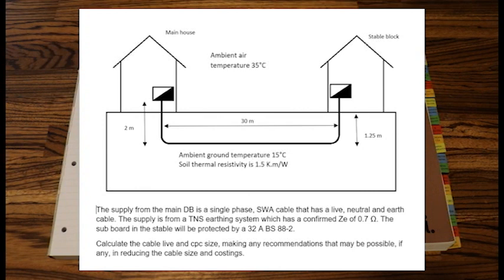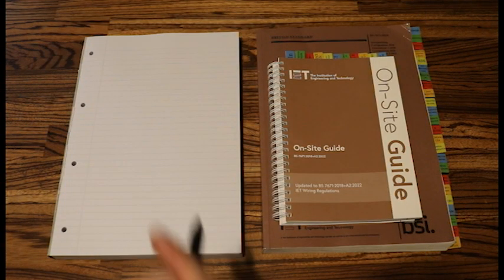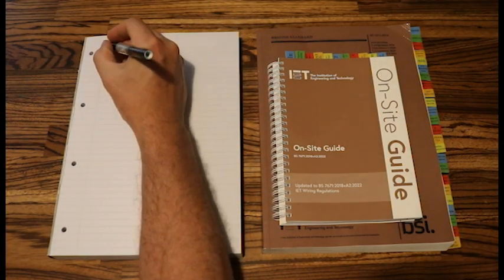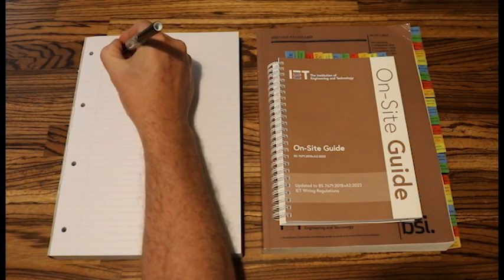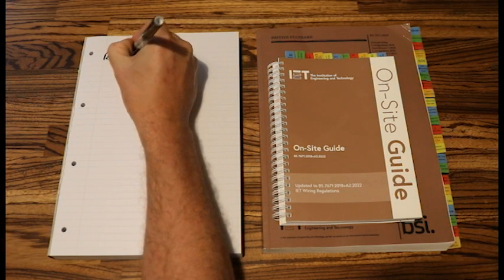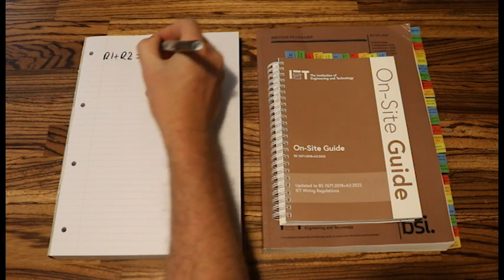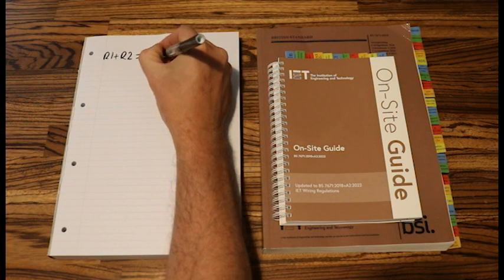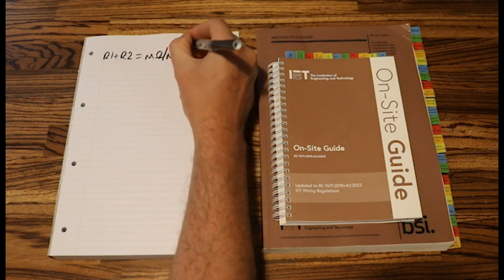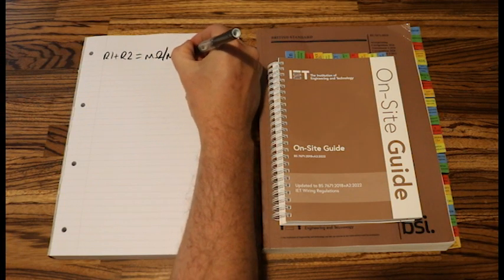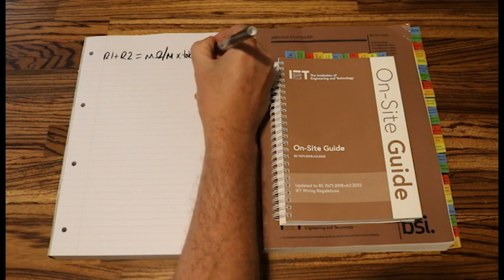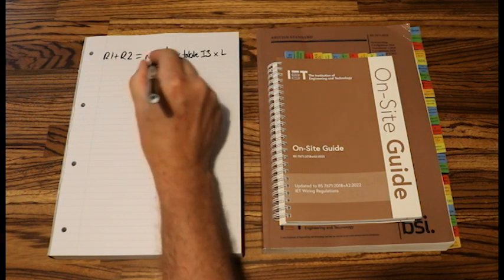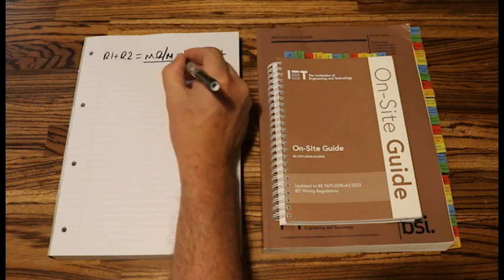So we need the formula for R1 plus R2. The formula is milliohms per metre times table I3 times length all over 1000.